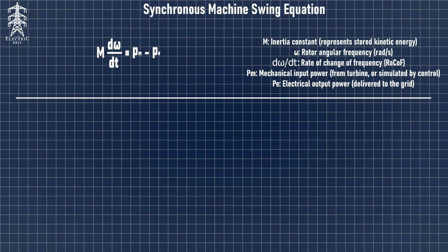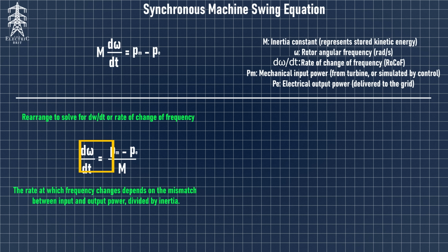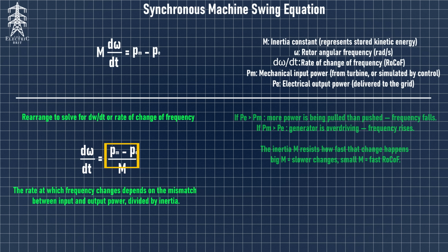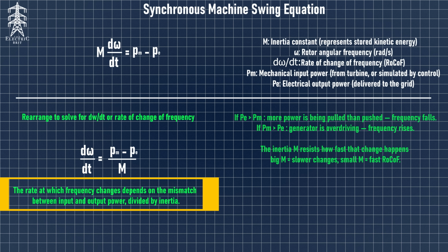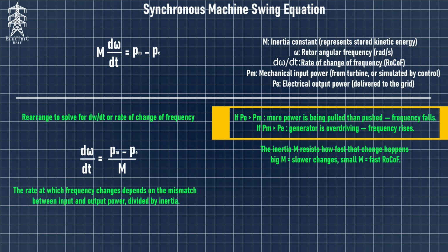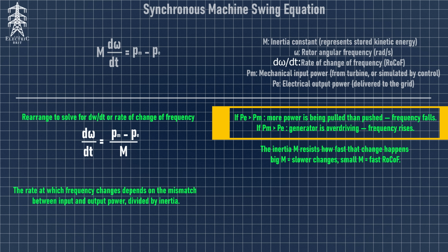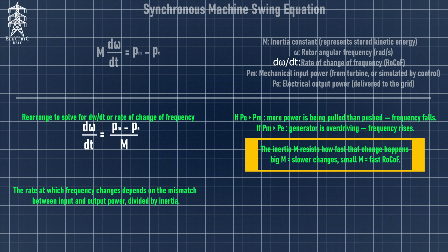We can then rearrange this equation to find out what our rate of change of frequency is. So delta omega over delta time is equal to power in minus power out, divided by our inertia constant, which simply put means our RoCoF depends on the difference between our power in and out divided by inertia. So if we have more power out than power in, our frequency falls, and if power in is greater than power out, our frequency rises. Changing our inertia, M, will dictate how quickly or slowly that frequency changes.